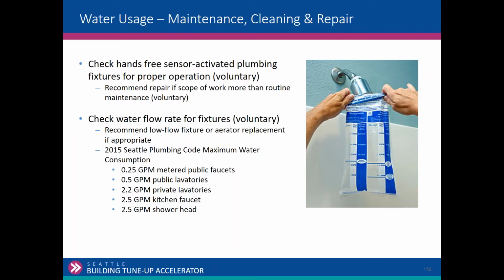You notice that the lab faucets are flowing 2 GPM and there's water everywhere. Then those are some simple recommendations where they can change aerators. They can adjust the automatic flush valves, the delay on the flush valves. Fairly simple water efficiencies. These are voluntary, but use your judgment. If you see water waste, note it. Put it into your report.